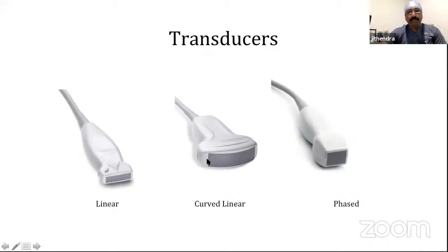Curvilinear probes usually have a lower resolution, but a better penetration. Linear probes have a higher resolution, lower penetration, and are high frequency probes. Curvilinear probes are lower frequency, with better penetration and lesser resolution. And the phased array probe is commonly used for echo, as well as for scanning the thoracic cavity and abdomen.